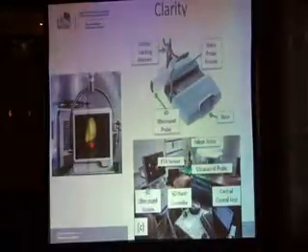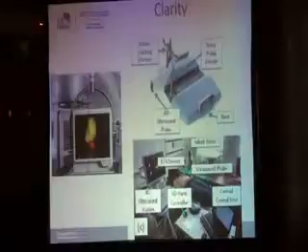If the position of the patient exceeds this threshold, the machine stops giving the treatment. It's an intra-session correction.